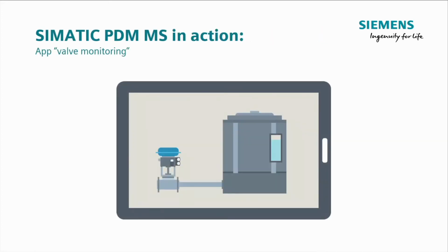So we're going to have a look at the pneumatic valve positioner. And as I said, its prime job is you send it a set point, it opens that valve, and you can use it for control or modulation. You can also use it to monitor diagnostics. So if you've got an on-off valve, you could use the valve positioner on a pneumatic valve just to open and close the valve, but what it's doing as well is monitoring the diagnostics of that on-off scenario.